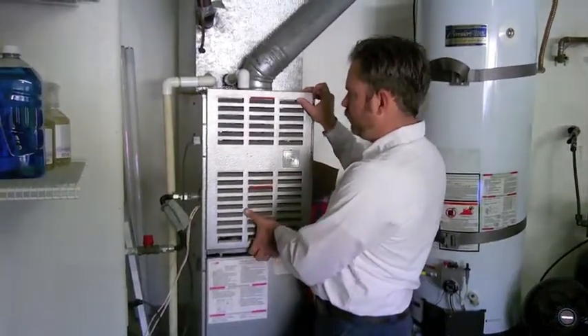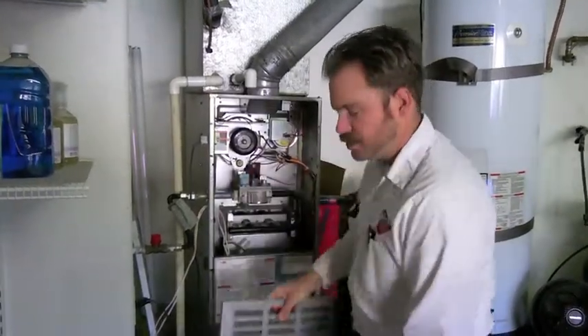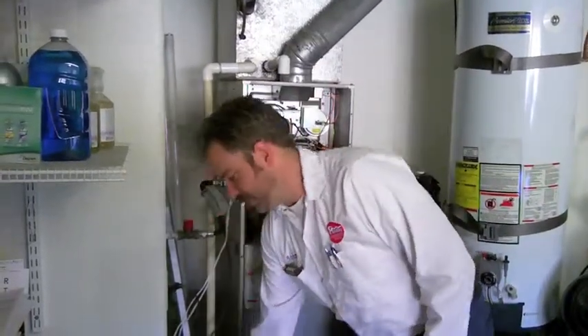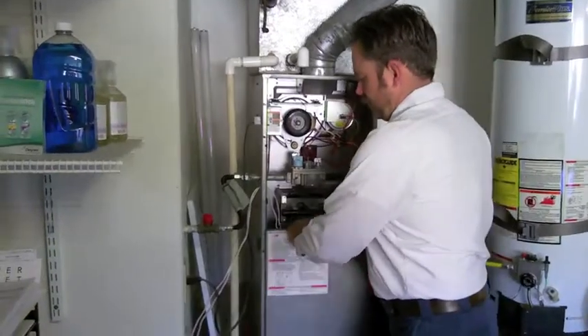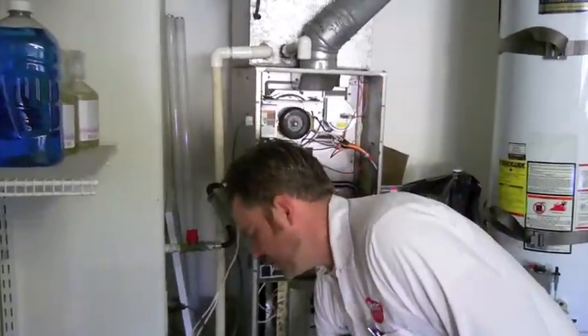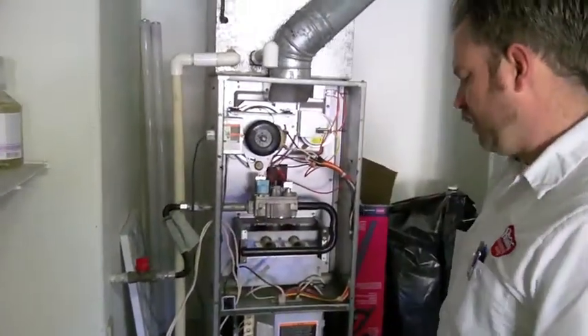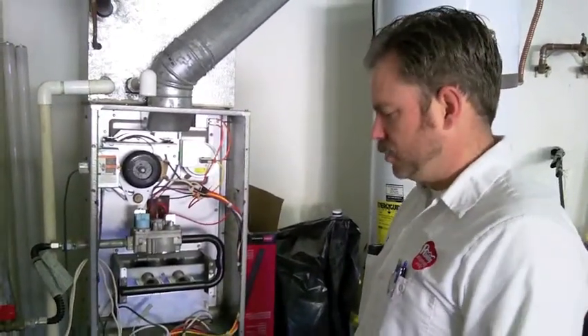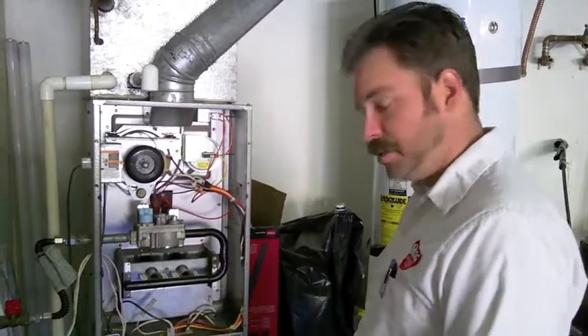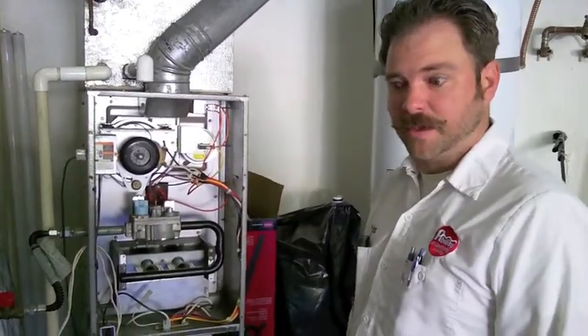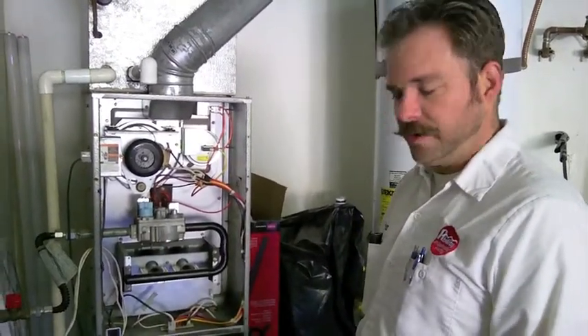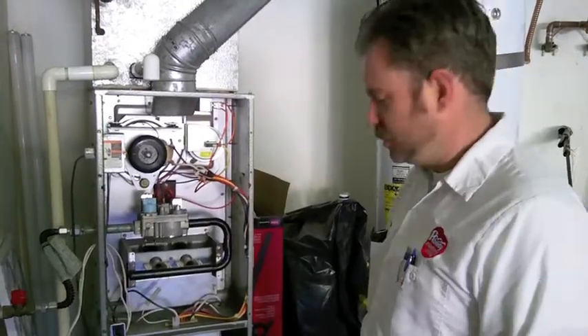You want to open the furnace up. This one's in a garage, so it makes it nice and easy. A lot of the time when they're in the garage, the doors just pop off. If they're in an attic, they'll typically have screws to hold the doors together. You want to replace those screws after you take them out because if the doors fall off, it can cause safety issues.